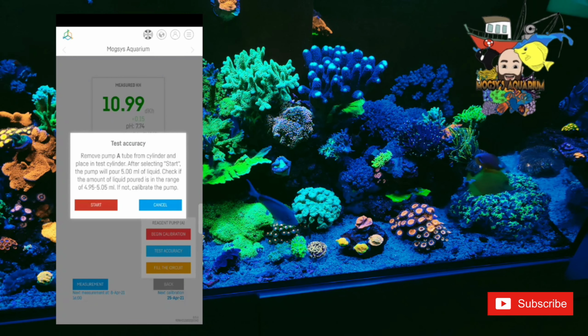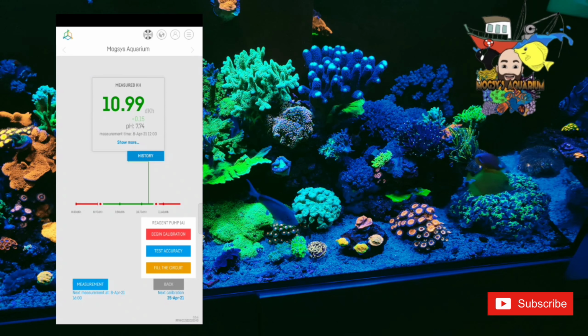And then you test accuracy again, but this time it will only dose 5 ml of the reagent. And don't forget to tip the reagent back into your reagent solution. It is expensive stuff, but at the end of the day, you need it to be spot on. The pH probe I wasn't really that bothered about, but this is a must to get a better, more accurate reading. And then empty is just, if you don't want to have anything in your test vial, you press empty and it empties it out.